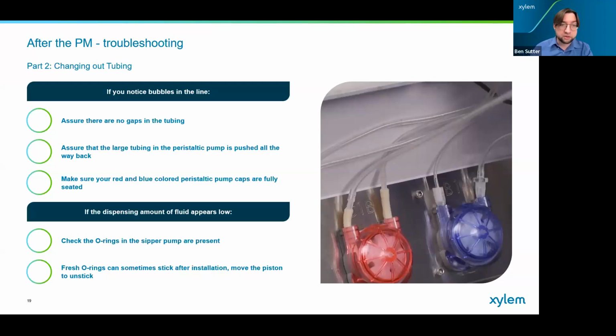Now, if the dispensing amount of fluid appears to be low after we perform our service, you want to check the O-rings in the sipper pump and make sure that those are present, because sometimes that can cause a leak and cause too little fluid to be dispensed. And sometimes fresh O-rings can stick after installation, and you have to move that piston a little bit to unstick it. Fresh rubber can be very, very sticky until you get it to move that first time. We're going to see that in the next step here. That being said, those are my follow-on tips.